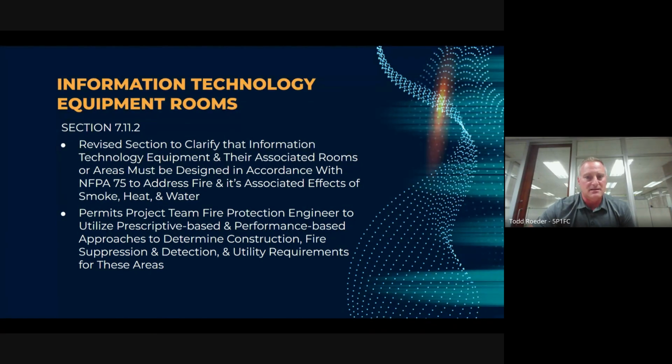In any case, the fire protection approach still must be based on the evaluation of the fire risks and the hazards associated with that ITE, the application, the services, continuity planning, and restoration capabilities of those spaces. So this section's been revised to allow some outside-the-box thinking, more risk-based scenario thinking, specific to the application at hand versus sticking to those typical prescriptive-based requirements that we have in the past.